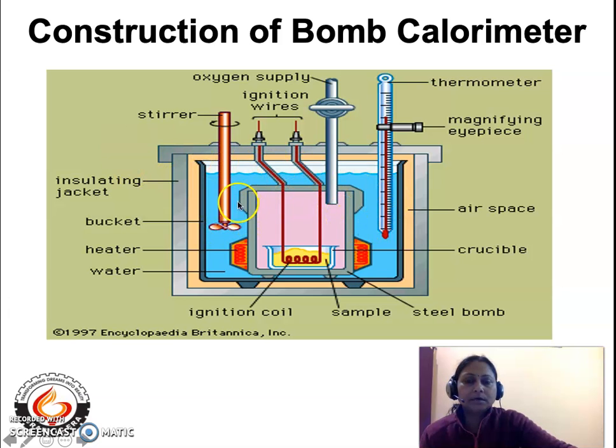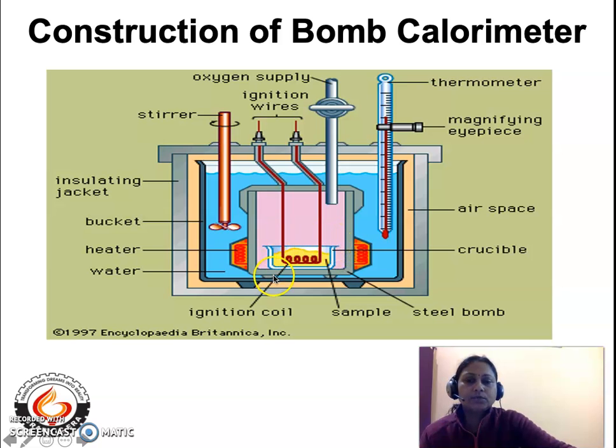The bomb is covered with a lid that tightly covers the bomb, and the lid is equipped with valves for the entry of electrodes. These two electrodes can be seen as red lines entering the bomb. Between the two electrodes there is an ignition coil made of magnesium wire. A crucible made of either steel or fused silica is placed inside the bomb, and this crucible contains a definite amount of fuel for which the calorific value has to be determined.